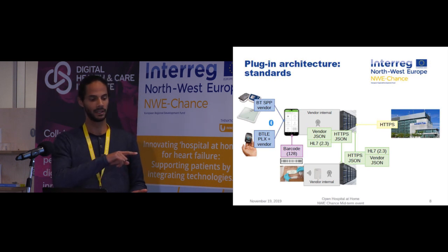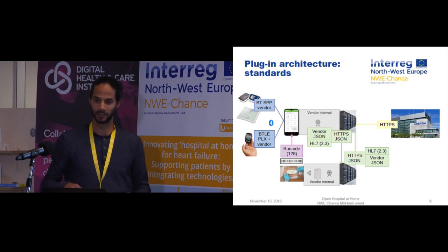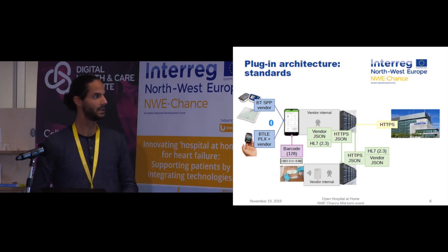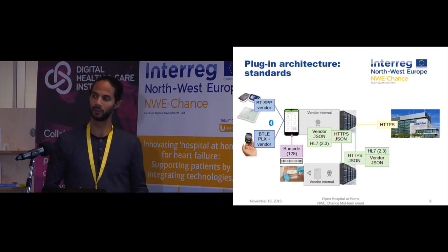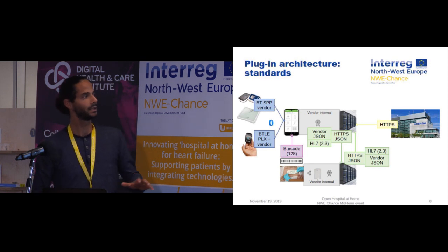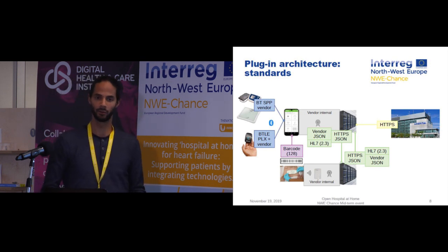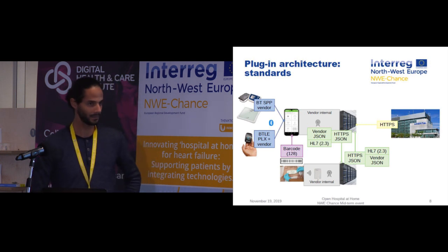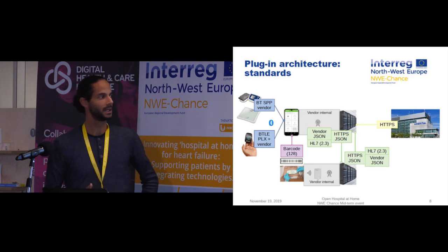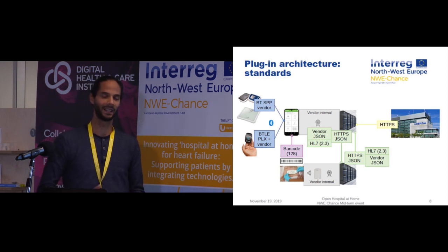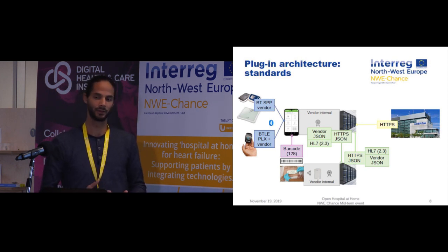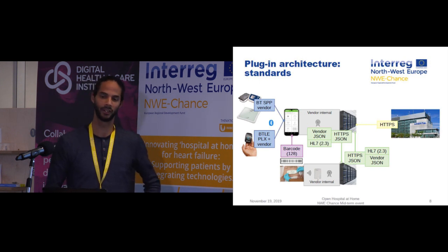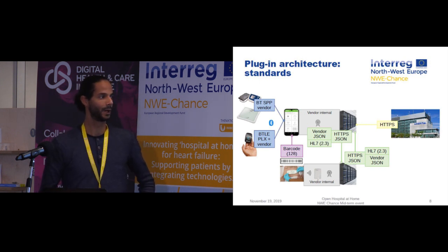For example, if you want the pulse waves to appear in your system, you're not going to get it through the PLX profile. The only place where we really had the freedom to determine our interface is in the back end, where we chose a middle ground technology or protocol, HL7. This is a very well-known protocol, even though it doesn't exactly specify how you should transfer your data. You still have to talk to each other, but at least it's widely recognized.